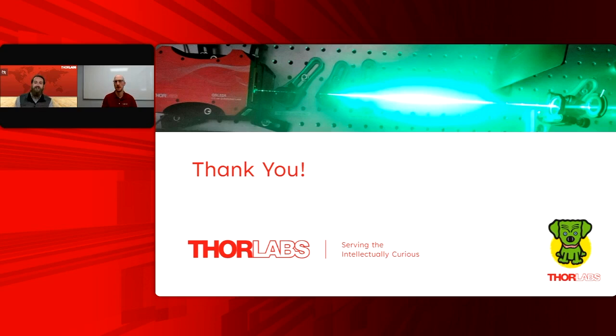That's right. And one thing I didn't mention earlier, the reason why you want to scan at all for a LIBS application, if you're not moving the laser across the surface of the sample, you will very quickly ablate all of the material in the focus. After 1 or 2 seconds, the laser isn't hitting the sample anymore because it's destroyed everything in the focus of the beam. And so your signal goes to nothing quite fast. And so that's why you need to constantly be scanning, or else you'll simply drill through the material and now you're not getting plasma anymore.